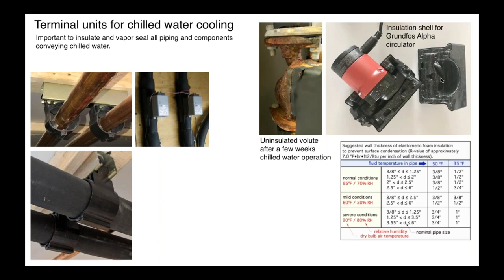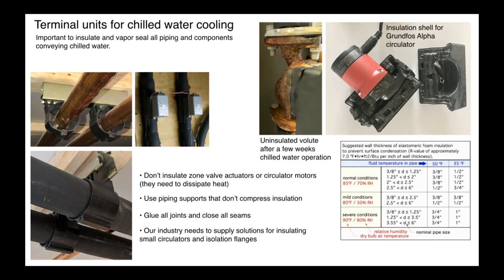In Hydronics 27, there's a chart that gives you an idea of how much R value or wall thickness you need with elastomeric foam insulation, depending on what your operating conditions are. In general, it doesn't have to be a lot. A quarter inch, 3/8 of an inch, half inch is very, very adequate, if your goal is simply to stop condensation, okay?